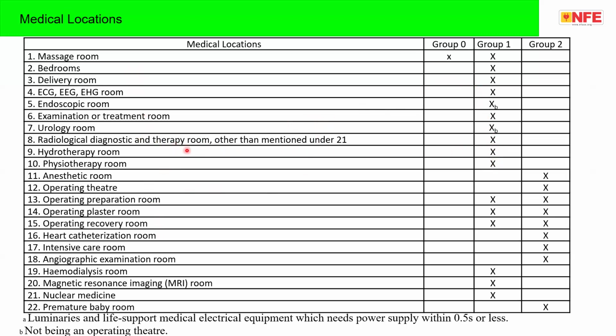For example, hydrotherapy room is a group 1 location. Operation theater is a group 2 location. Anesthetic room is a group 2 location. Angiographic examination room is a group 2 location. Nuclear medicine is a group 1 location. So basically, different locations are very well defined in the standard. The safety measures required in each of these locations vary. Group 1 locations need additional safety measures. Sometimes group 2 locations need some more extra safety measures.